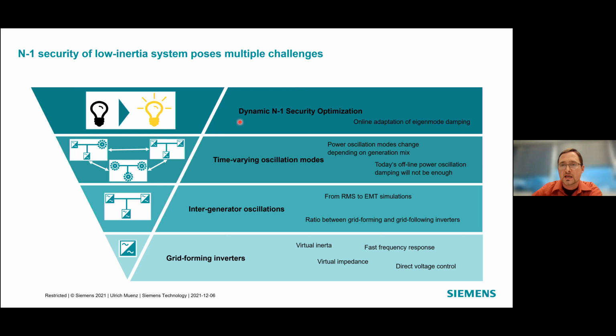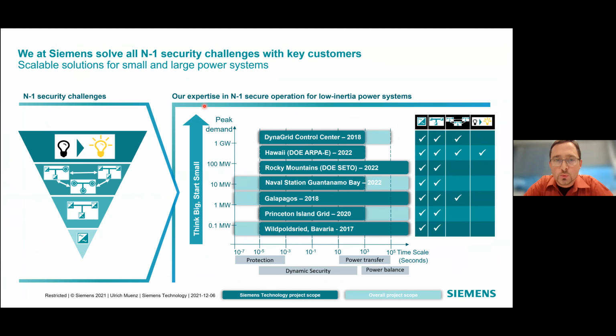That's what we call dynamic security optimization. N-1 security means the system can withstand any single outage - a power plant or power line - without a larger blackout. This needs to be done online to make sure the lights stay on and we don't have a big blackout. Now, what is the expertise, or what have we done?